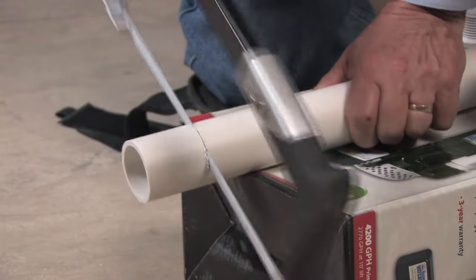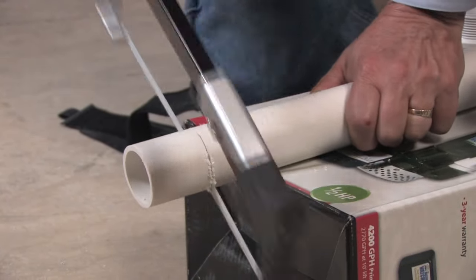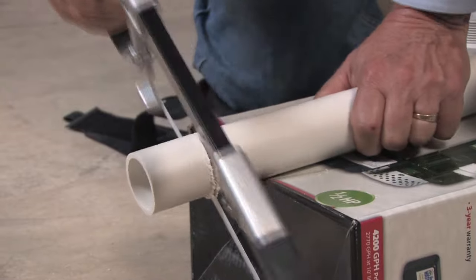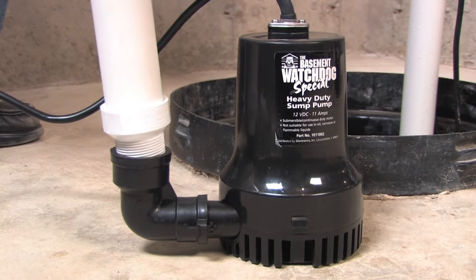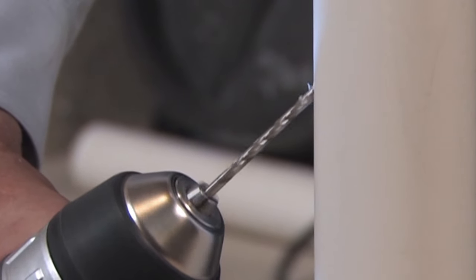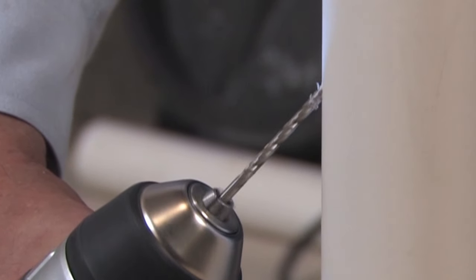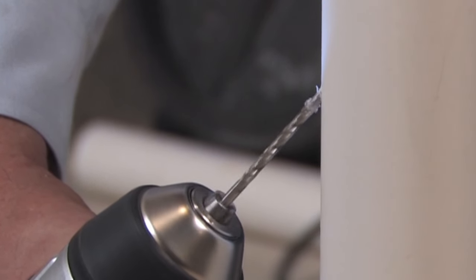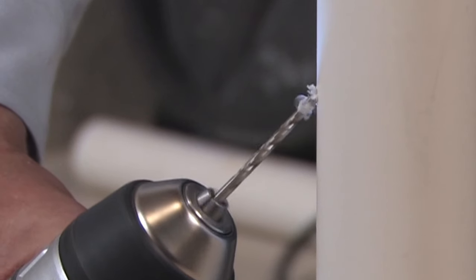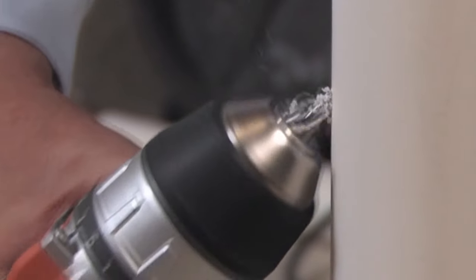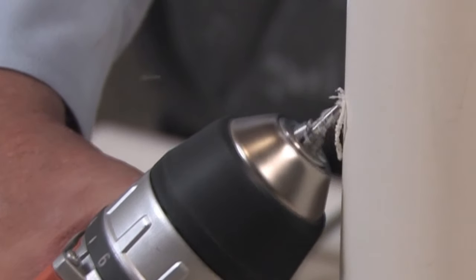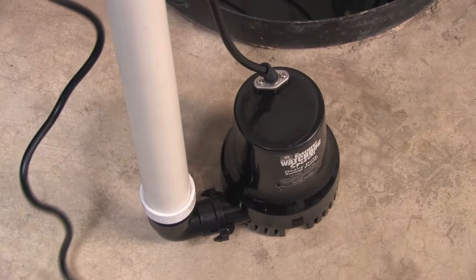Cut a piece of pipe that reaches from the bottom of the sump pit to about one foot above the floor. Glue the adapter onto that pipe and then screw it into the backup pump. Drill a one-eighth inch hole in the pipe above the backup pump at a 45-degree angle toward the bottom of the sump to avoid water splashing outside the sump pit. If this hole is not drilled, an airlock may prevent the pump from working.